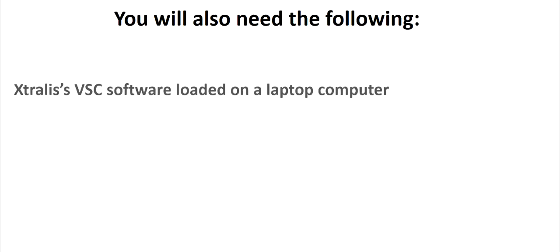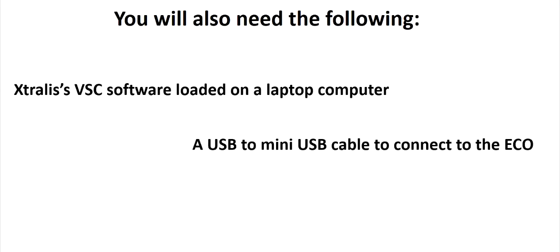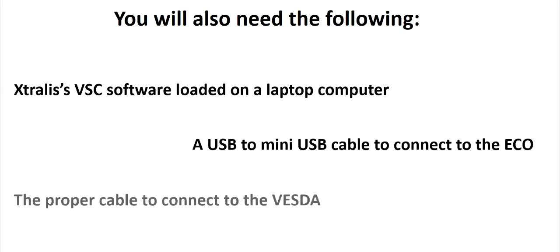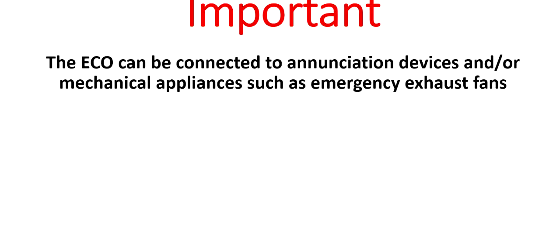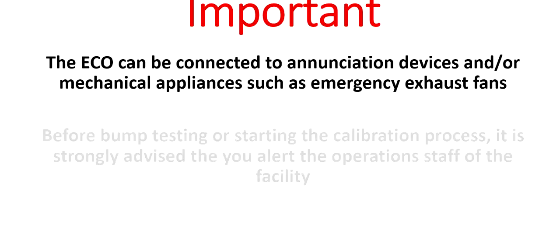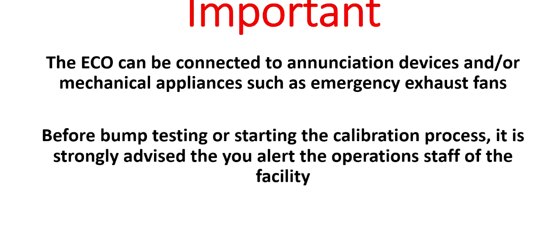You will also need the following. If you do not have it, you can download a current version of Xtralis' VSC software from the Xtralis website library or contact your local Xtralis representative. The ECO's output can be connected to a number of different devices. Before bump testing or calibrating an ECO, alert the operations staff of the facility.